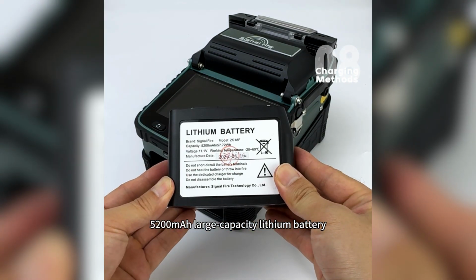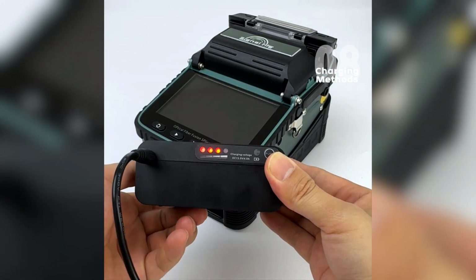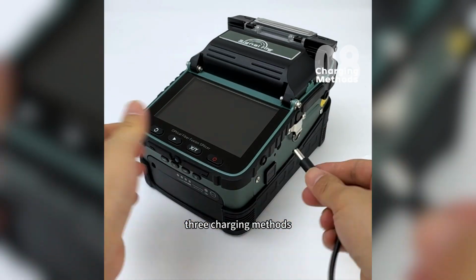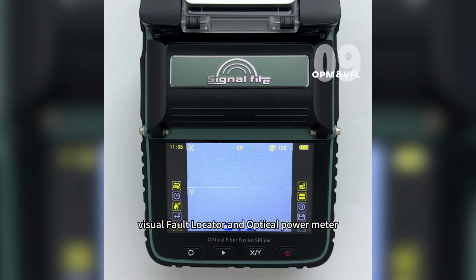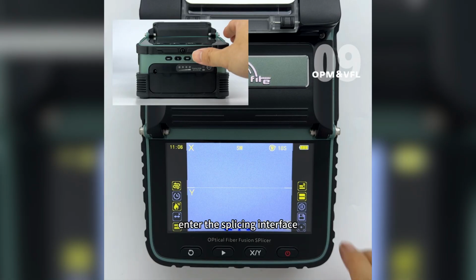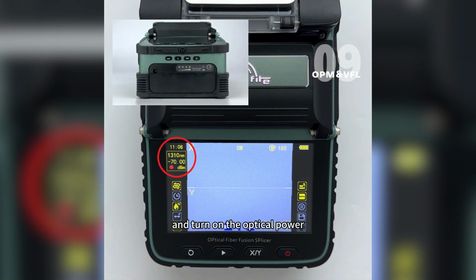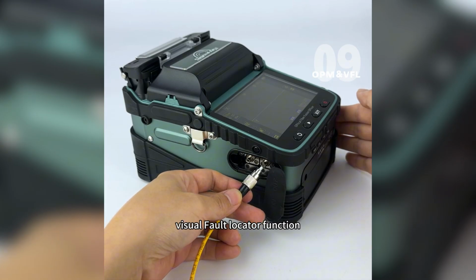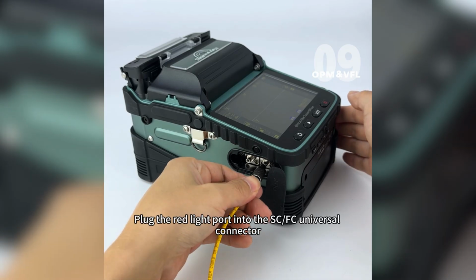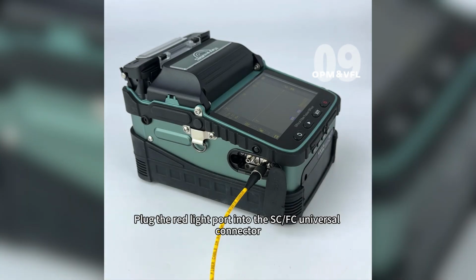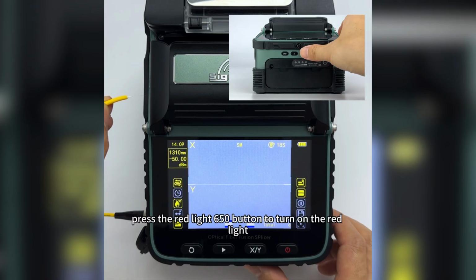5,200 mAh large capacity lithium battery, 2 charging ports, 3 charging methods. Visual fault locator and optical power meter. Enter the splicing interface and turn on the optical power and red light power switches. Visual fault locator function: plug the red light port into the SC or FC universal connector. Press the red light 650 button to turn on the red light.